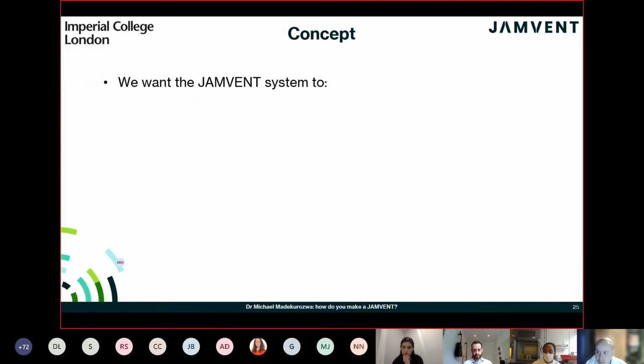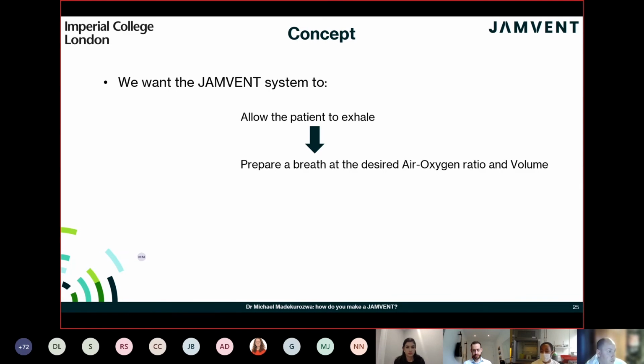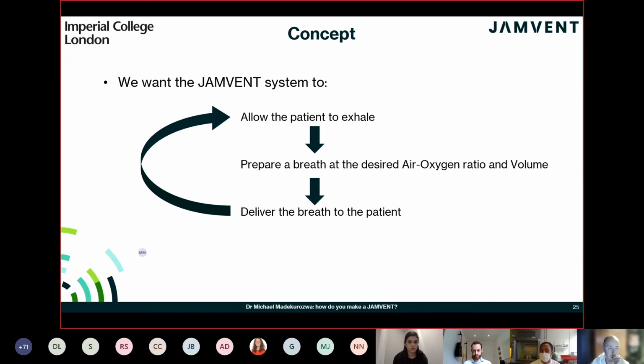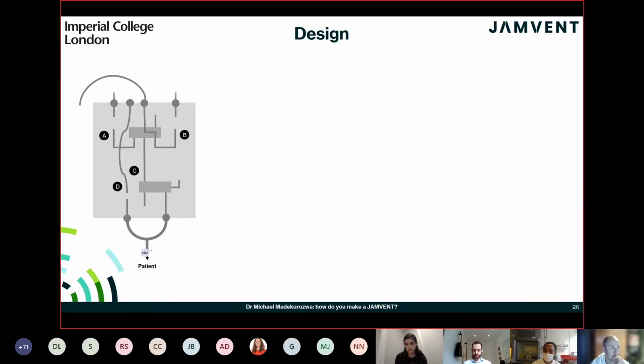So I'll go through a little bit of the concept of how the JAMVENT system actually works. So the first step is to allow the patient to exhale. After the patient has exhaled, the JAMVENT system prepares a breath at the desired air to oxygen ratio and volume. Next, the system delivers the breath to the patient. And then this cycle repeats. So the patient is allowed to exhale, a breath is prepared, and then the breath is delivered to the patient. And this is what ventilation is.